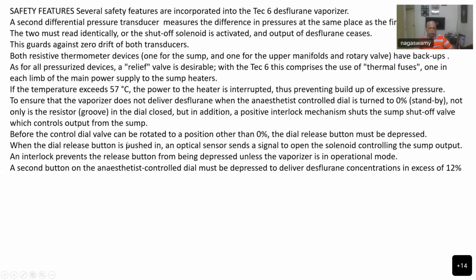And before the control dial valve can be rotated to a position other than zero, the dial release button must be depressed. That is common for all the vaporizers, not only Tec 6. In every vaporizer, you have to first press the button and then only you can turn the dial on. When the dial release button is pushed, an optical sensor sends a signal to open the solenoid controlling the sump output valve. That is the shut-off valve. An interlock prevents the release button from being depressed unless the vaporizer is in operational mode. And a second button on the anesthetist control dial must be depressed to deliver desflurane concentration in excess of 12%.